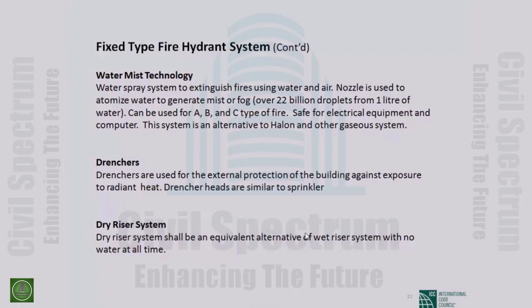There is another one which we call the water mist system technology. This is a very special type of water spraying system with a high pressure and very special nozzle. The nozzle will atomize the mist.